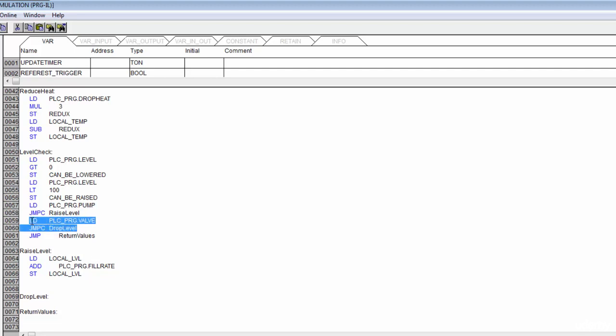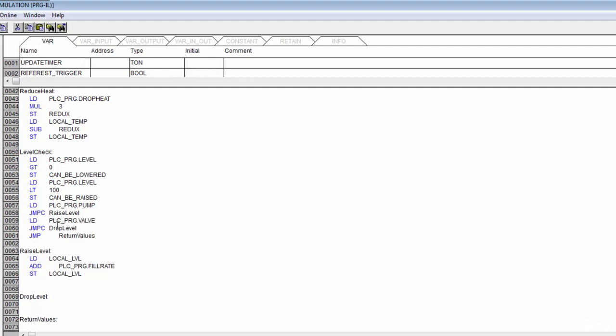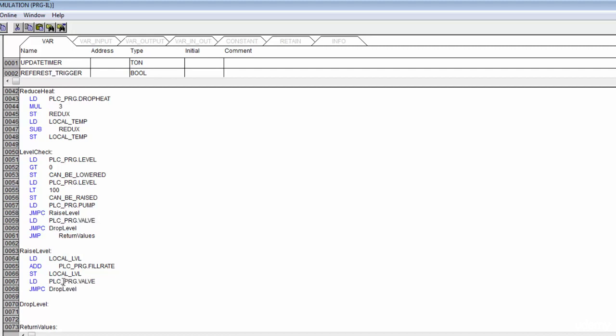We need to check our valve somewhere outside the raise block, so let's cut that out and come down to drop_level. We also need to check if our valve needs adjustment, because theoretically both the pump could be running and the valve could be open. So we'll either jump to drop_level or jump to return_values.